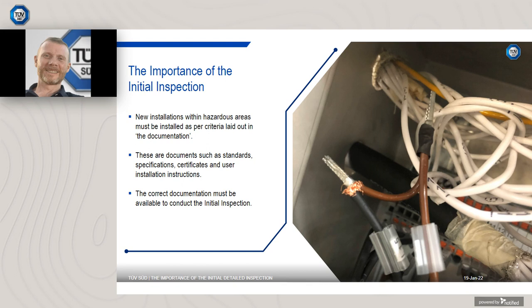A detailed inspection at a supplier factory picked this fault up. The terminals installed within the Ex connection box did not match a general arrangement layout, nor the wiring diagram. The installer, rather than query it, made his own links and altered the design. No management of change nor query was submitted. The modified crimps were not fit for purpose, and the solution was not within specification. The supplier had to redo the junction box as per design at his cost.